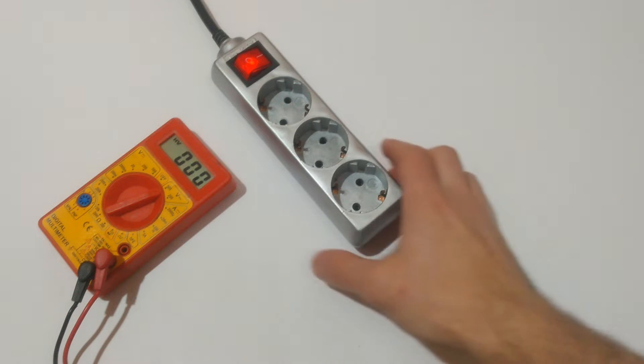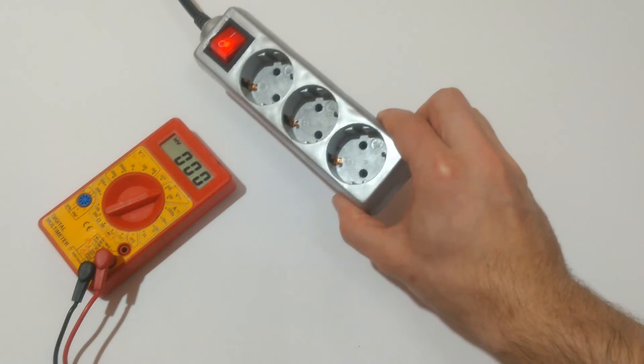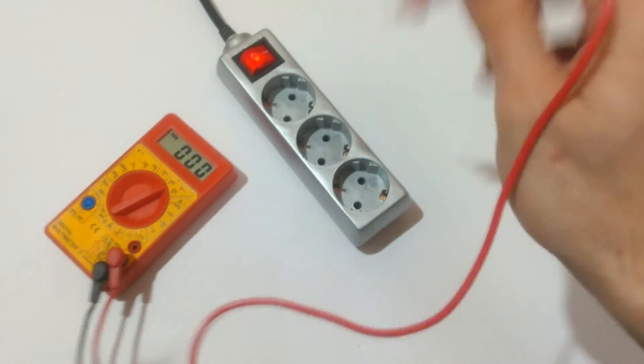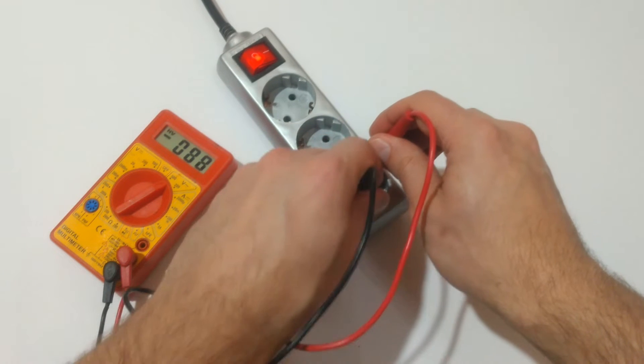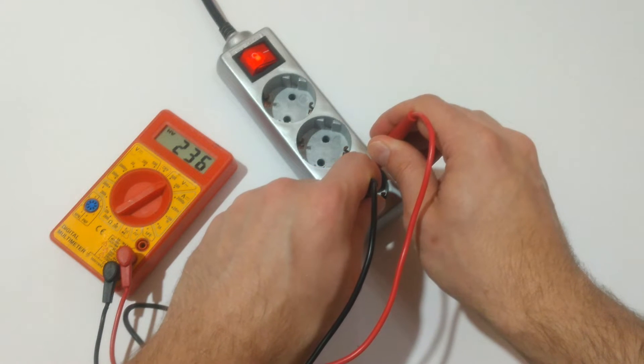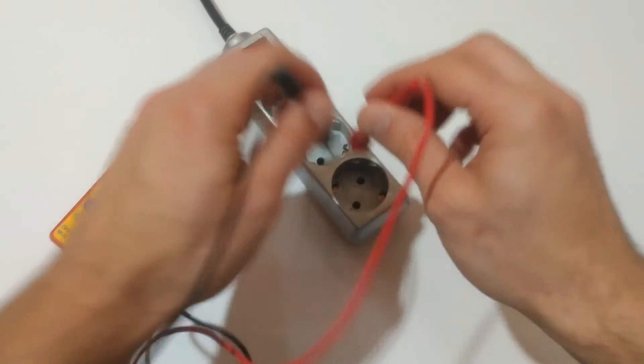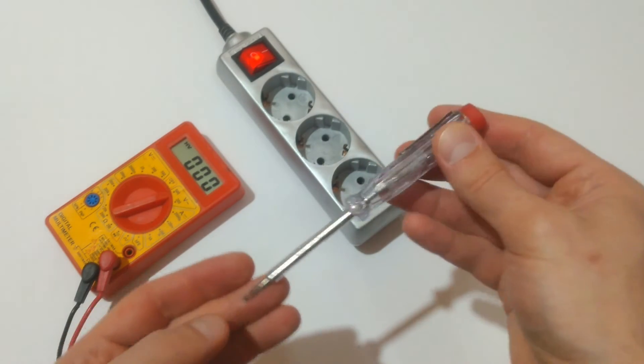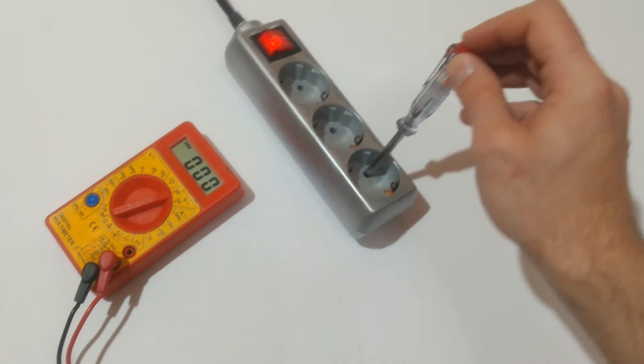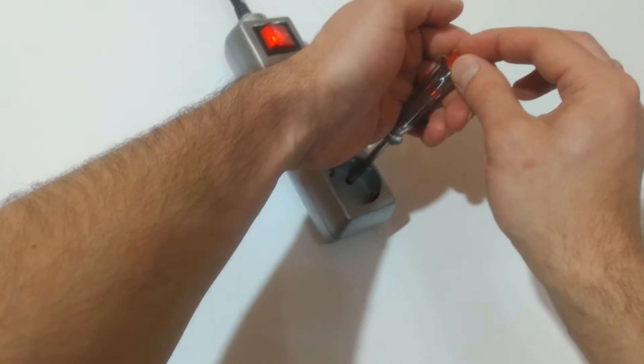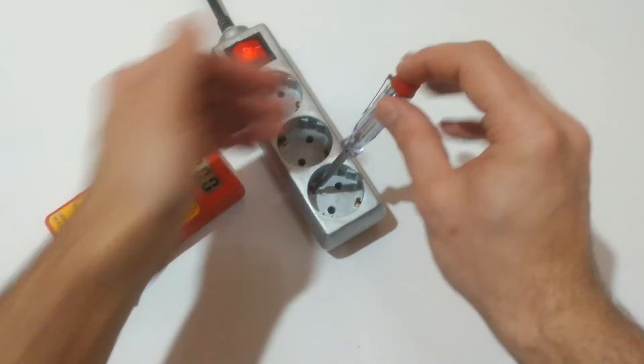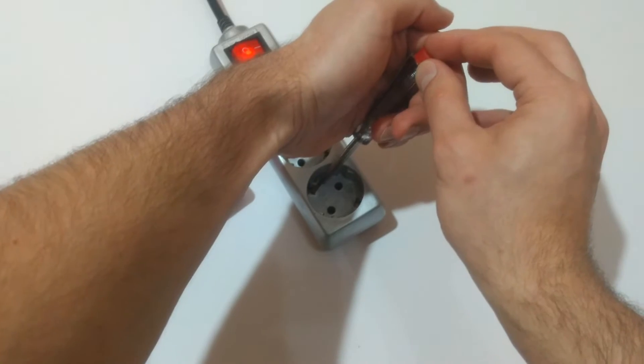Second test will be on this energized power strip. Let's measure its voltage. 235, 236 volts. Now let's pinpoint the live conductor. And this one here is the live. Neutral, neutral, and grounding.